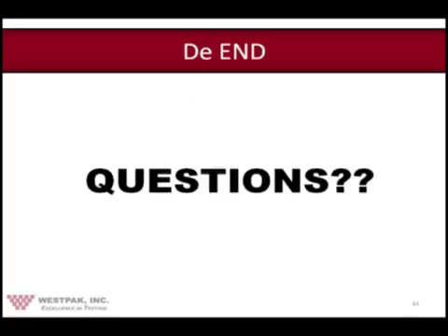I should mention that there was a question at the morning webinar session that had to do with the effect of pressure on the accelerated aging process, and the answer to that is there is no effect unless something is very compressible at very minor pressure changes, and I'm not aware of anything at all. Neither ISO 11607 nor any of the other documents that I mentioned, especially ASTM F1980, have any mention of pressure, either atmospheric pressure or absolute pressure.